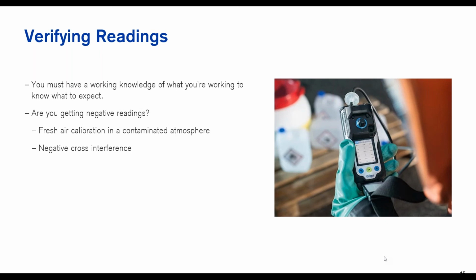There may be, depending on the sensor, cross interference that just naturally does that. So I may have a sensor designed to read chemical A, but if it sees chemical B, it's going to give you the opposite of the spectrum. So rather than 5 parts per million, it may give you a -5. Again, referring back to your technical specifications, a lot of times that sensor information will tell you what those potential negative cross interferences are.